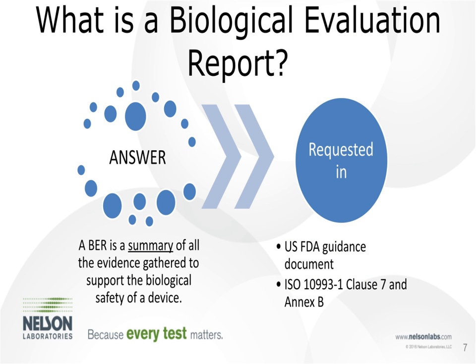So what is a BER? It is really a summary of all the evidence gathered to support the biological safety of a device. This is specifically requested in the US FDA guidance document and in Clause 7 and Annex B of ISO 10993-1, where they outline the specific requirements that help you write your BER.